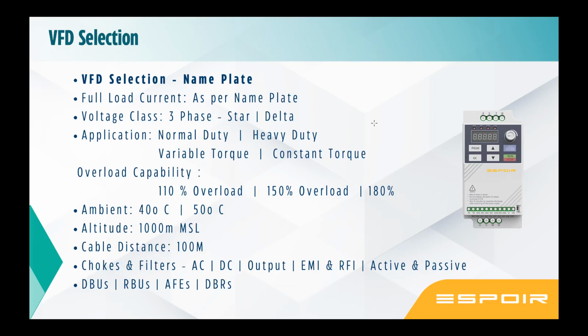Now, if the regen mode is very constant, very intermittent, very frequent, you can use a regenerative braking unit. Instead of wasting that energy, you can connect it to the grid. If your system is large and your braking cycle is long, you can go for an RBU system. Now, RBUs are coming out with AFEs. AFE is the next step, which is an active front-end system. AFEs are a parallel drive. It's like two drives working together, and one drive works on the motor, and the other drive, when there is a regen mode, directly transfers the power to the grid. It works as an energy saving.